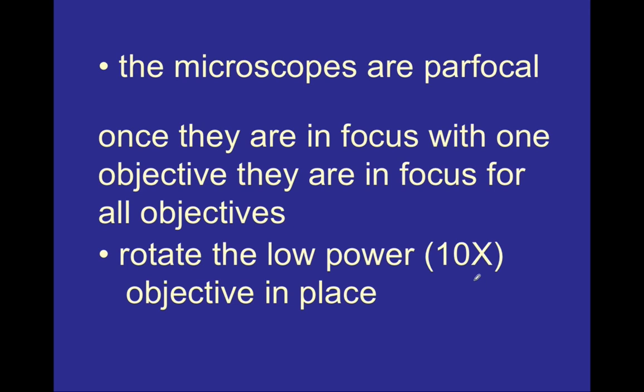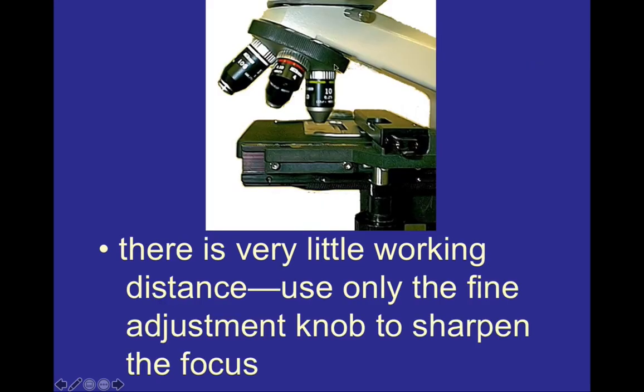There is another concept about microscopes that makes it much easier to stay focused when changing between objective lenses, and that is the word parfocal. Parfocal means that when one objective lens is in focus, all of the objective lenses are roughly in focus as well. So once you get the stage in the right spot for the scanning objective lens, you'll be just about in the right spot for the low power and high power objectives, and you will only need to make minor changes with the fine adjustment knob.